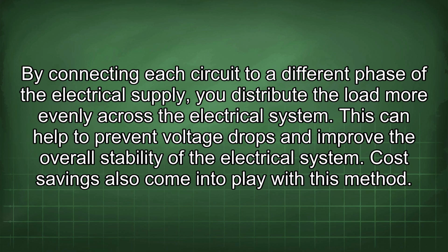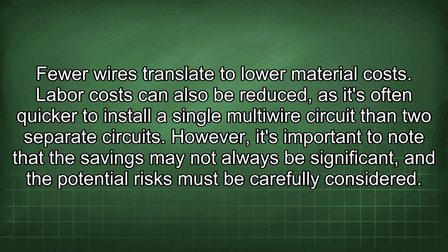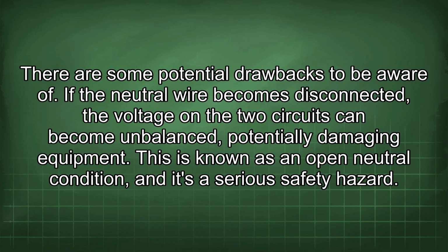Cost savings also come into play with this method. Fewer wires translate to lower material costs. Labor costs can also be reduced, as it's often quicker to install a single multi-wire circuit than two separate circuits. However, it's important to note that the savings may not always be significant, and the potential risks must be carefully considered. There are some potential drawbacks to be aware of.